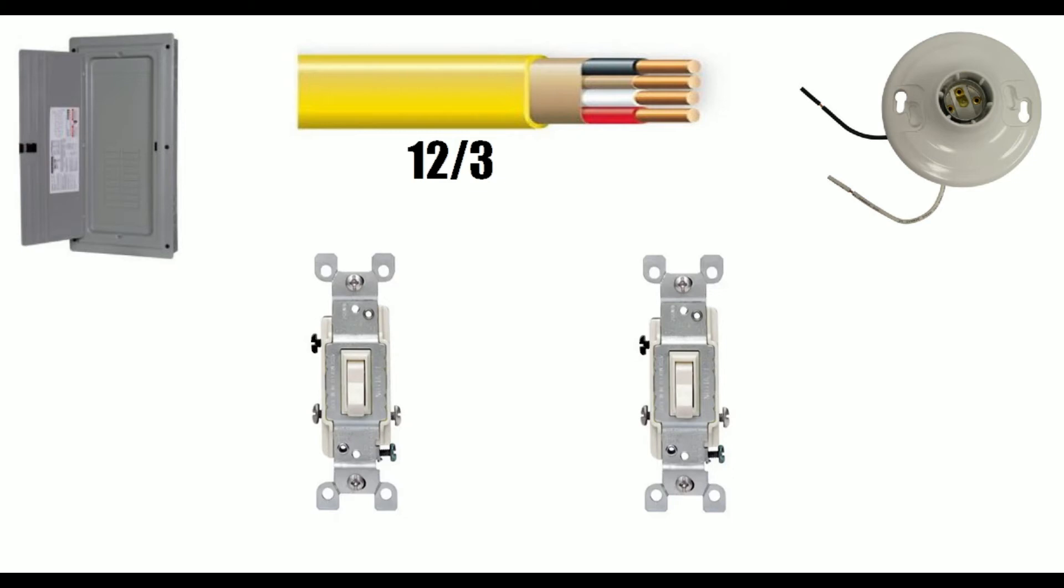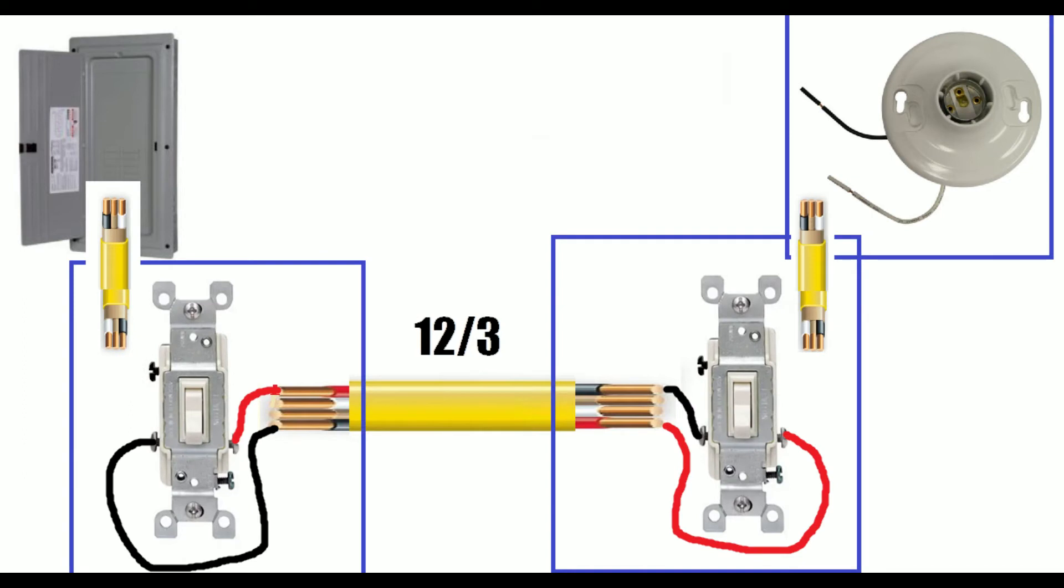Now, you don't have to use 12-3. You can use two sets of 12-2, but this is the simplest way to show you in a diagram. The two screws on your switch that are not black are called your travelers. You're simply going to connect them to each other with the black and red of your 12-3.